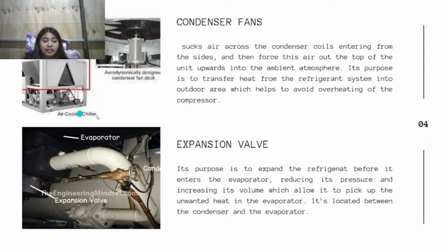Condenser fans. This is a condenser fan. It sucks air across the condenser coils, entering from the sides, and then forces air out the top of the unit upwards into the ambient atmosphere. Its purpose is to transfer heat from the refrigerant system into the outer area, which helps to avoid overheating of the compressor. So this is the expansion valve.